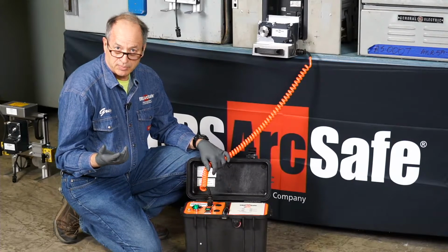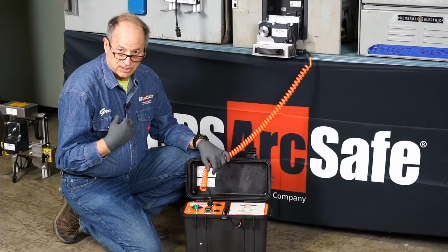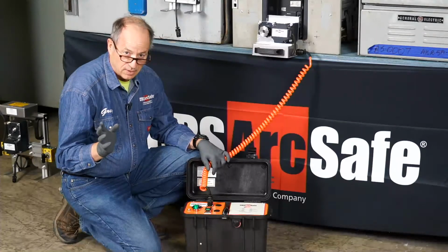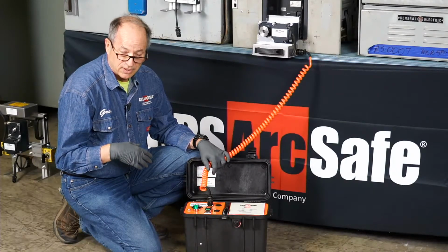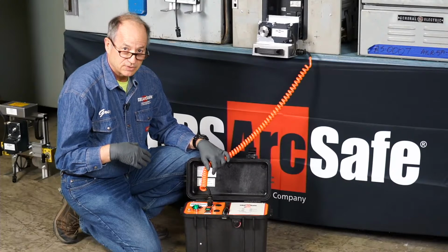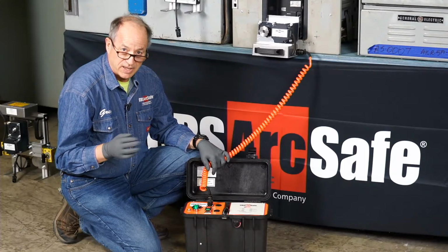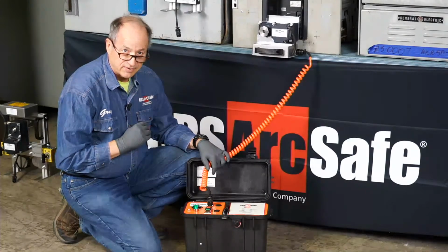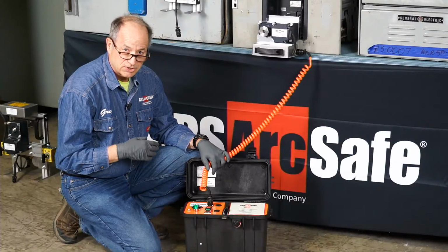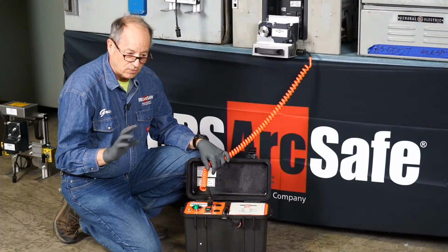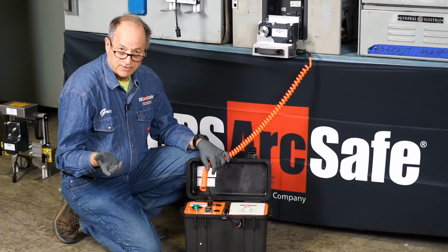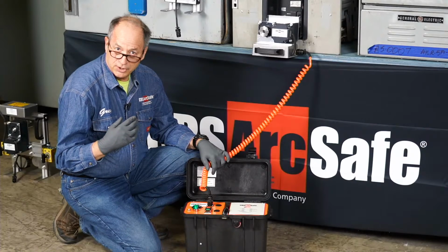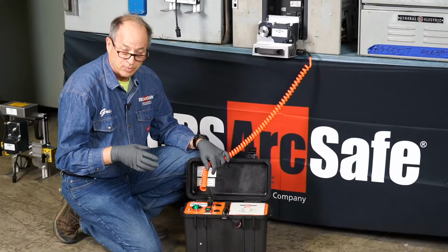I know that every Magnum DS breaker out there that's 3,200 amps and below should take under 10 foot-pounds to rack on and off the bus if everything's in good condition. So I could set a clutch on my RS1 or RS3 to around 15 foot-pounds, and I should be able to rack all of those without any problems.